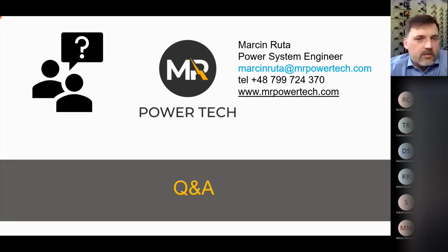I see there's also an ongoing discussion with Callum, but let me have a look. Downside of maintenance mode is that you still rely on someone turning it on and off as needed. Some room for human error to occur, but it's usually cheaper to implement an arc detection system. Well, the idea behind it is also that you have a lockout toggle. So you are the engineer that is going there, switching off things, you activate it, and you lock it with your lock. So there should be no one else activating this, because it's your breaker that you are working on. So you have to do it step by step by yourself.